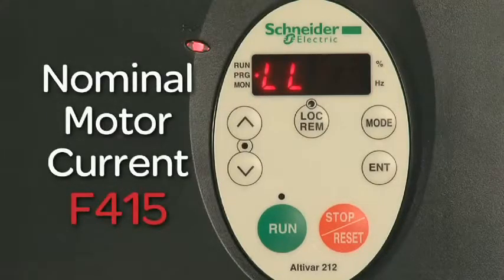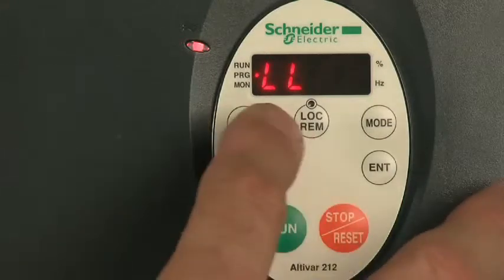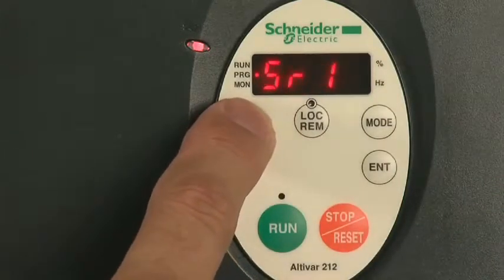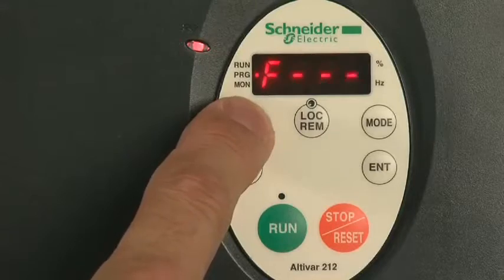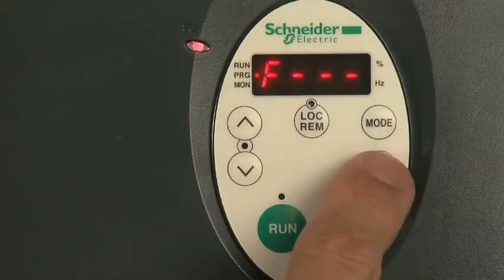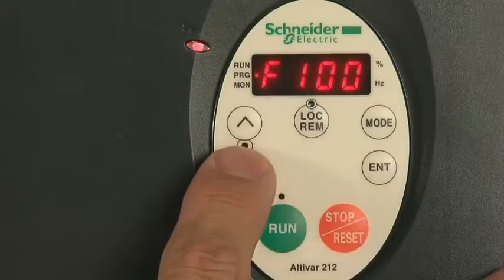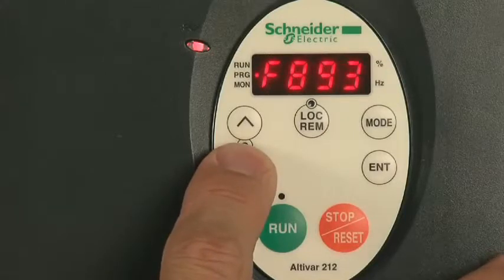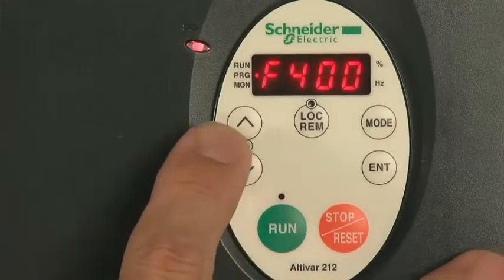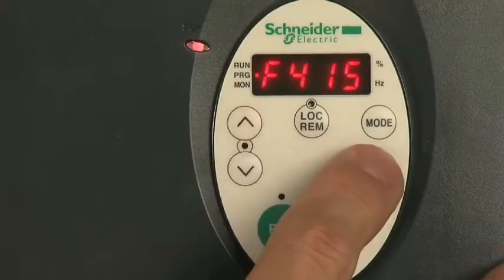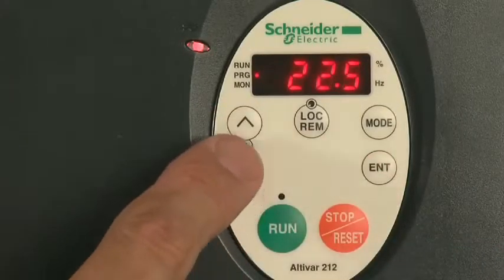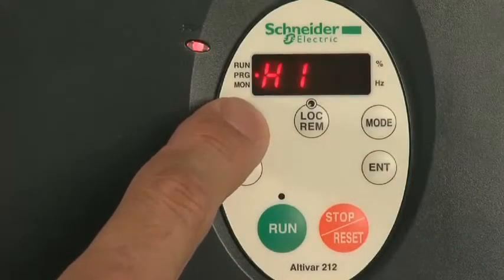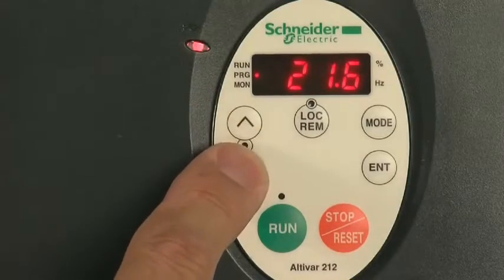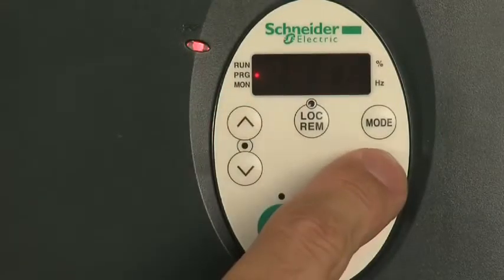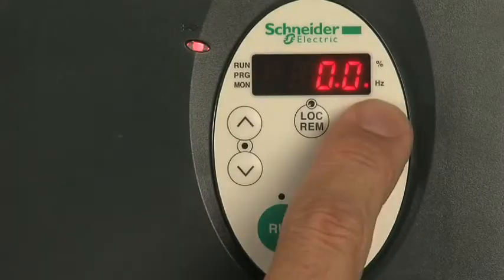Next, we will configure nominal motor current, parameter F415. Navigate to the F-dash menu. Press ENT. Use the arrow keys to navigate to F415 and press Enter. Use the arrow keys to navigate to the correct value equal to your nominal motor current from the motor nameplate. This value will be set in amps. Press ENT, then Mode to place the drive in run mode.